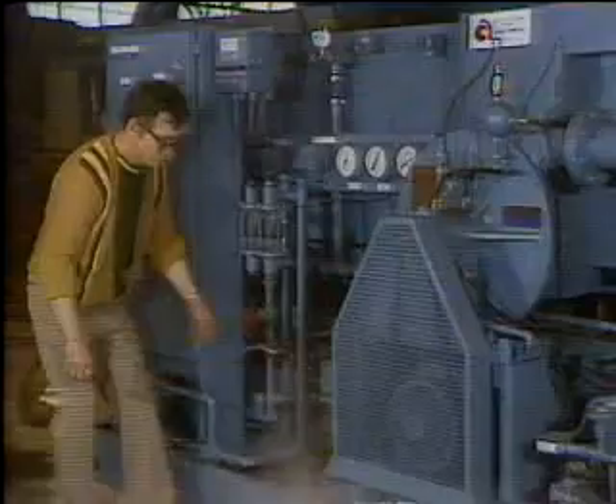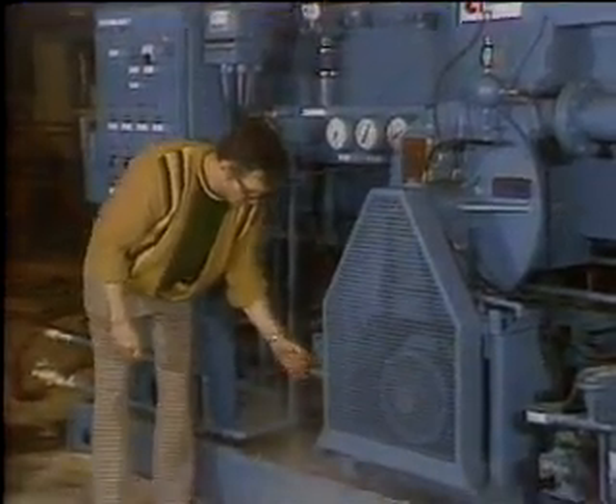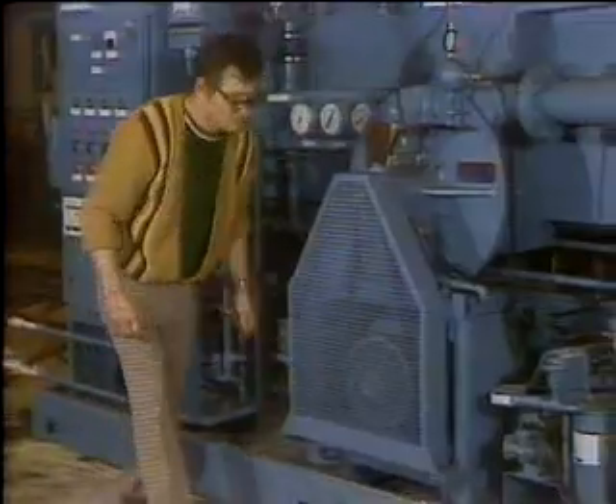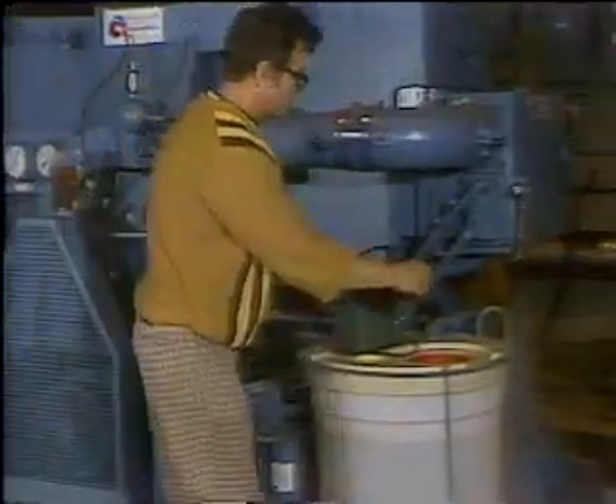Check the compressor drain valve. It'll blow steam and water for a little while, but should begin to blow only steam after a minute or two. When it does this, shut it off and close the vent condenser vent valve down to where just a wisp of steam escapes.